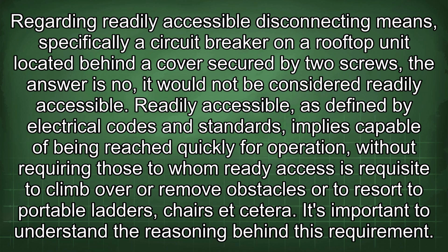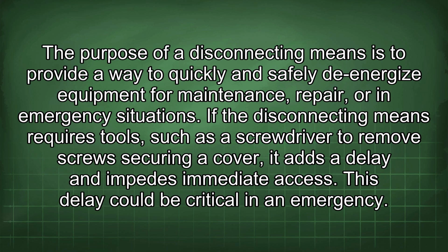It's important to understand the reasoning behind this requirement. The purpose of a disconnecting means is to provide a way to quickly and safely de-energize equipment for maintenance, repair, or in emergency situations. If the disconnecting means requires tools, such as a screwdriver to remove screws securing a cover, it adds a delay and impedes immediate access. This delay could be critical in an emergency.